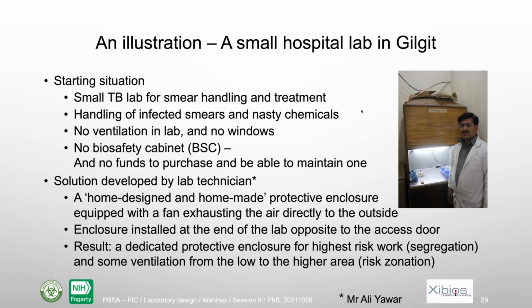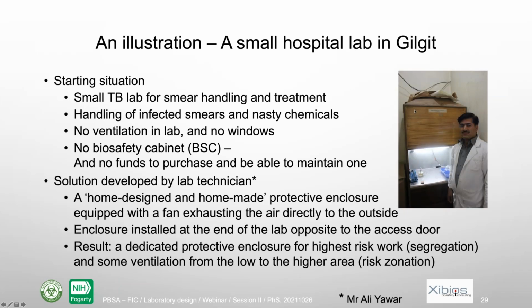Actually, it was a solution that was developed by one of the technicians who was working in that lab. That guy designed and built a kind of enclosure like this. It looks like a biosafety cabinet, but of course it's not a biosafety cabinet. It's not certified as such. It has a very clean work area. It has a window to protect from splashes, for instance. And inside of that box, there is an exhaust fan that is connected to the outside of the lab. And you put that cabinet at the end of the lab.